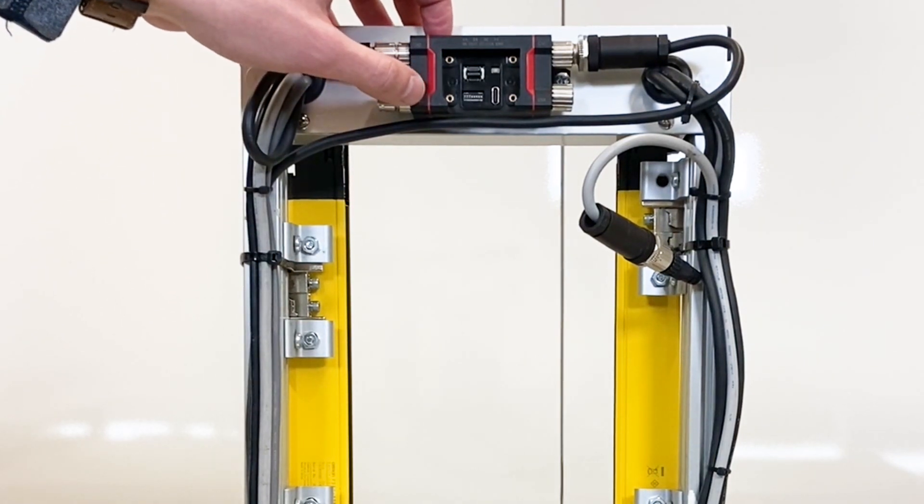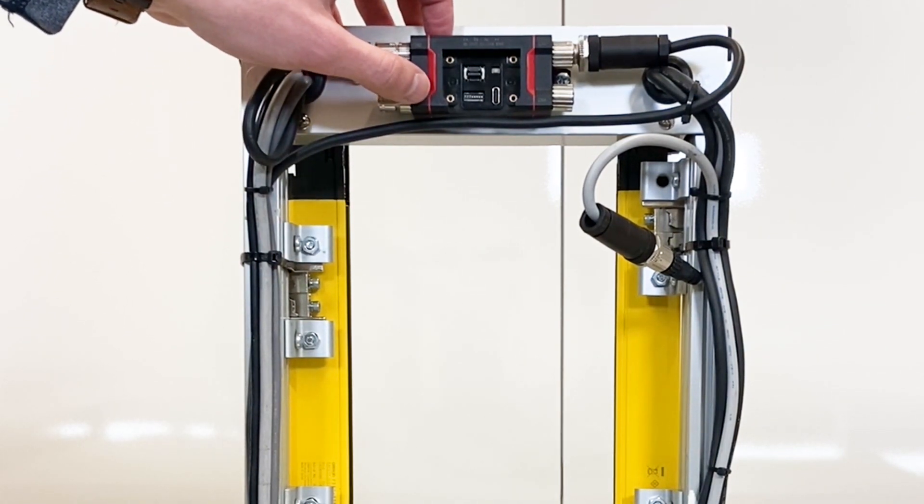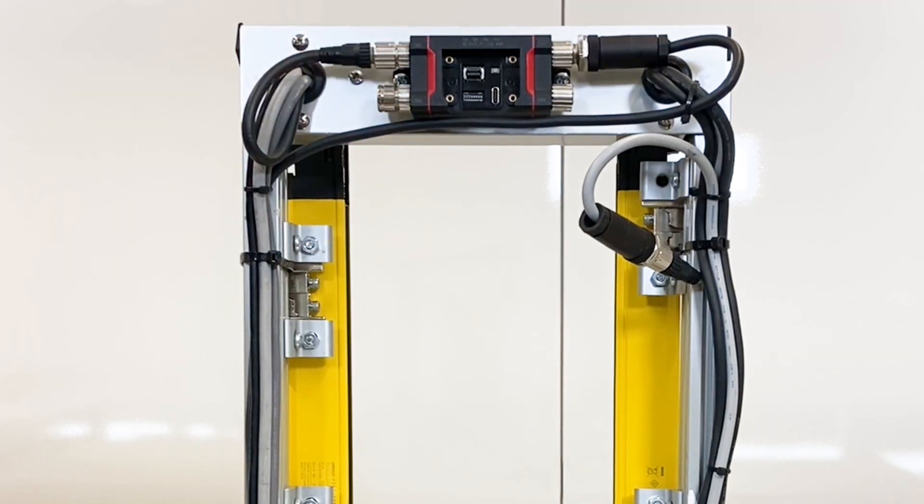DIP switch number 1 is going to put your light curtain into the lock state, DIP switch 2 is going to enable you to make programming changes with the DIP switch, and DIP switch 3 is going to enable EDM.